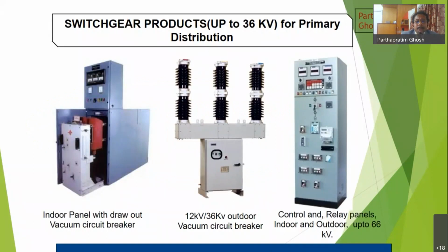There are various kinds of circuit breakers, medium voltage circuit breakers. The middle one is the outdoor circuit breaker, and the separate control panel drives the circuit breaker, enabling it to switch on and switch off. And the left hand side is an indoor circuit breaker where the control panel is inbuilt in the same panel.